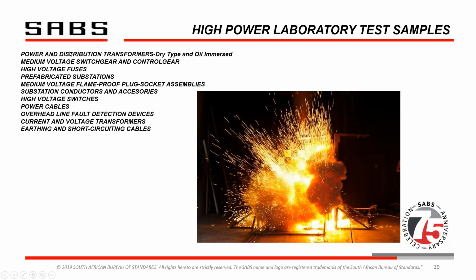This is what you can test at the lab: power and distribution transformers, dry type or oil immersed, medium voltage switchgear and control gear. As I said, Actom switchgear have already used the facility. And Greg White's comment to me was that the facility is extremely important for them. High voltage fuses, prefab substations, medium voltage flame-proof plug socket assemblies, substation conductors and accessories, high voltage switches, power cables, overhead line fault detection devices, current and voltage transformers, earthing and short circuiting cables.